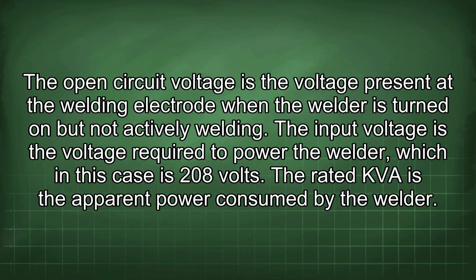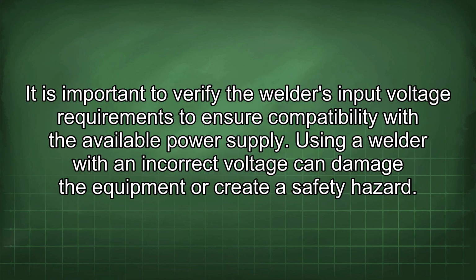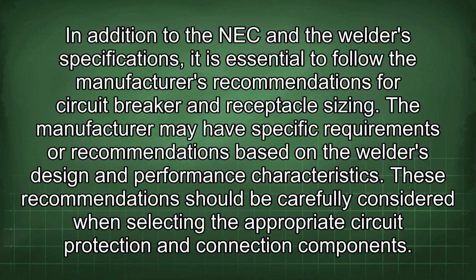The input voltage is the voltage required to power the welder, which in this case is 208 volts. The rated kVA is the apparent power consumed by the welder. It is important to verify the welder's input voltage requirements to ensure compatibility with the available power supply. Using a welder with an incorrect voltage can damage the equipment or create a safety hazard. In addition to the NEC and the welder's specifications, it is essential to follow the manufacturer's recommendations for circuit breaker and receptacle sizing. The manufacturer may have specific requirements or recommendations based on the welder's design and performance characteristics.